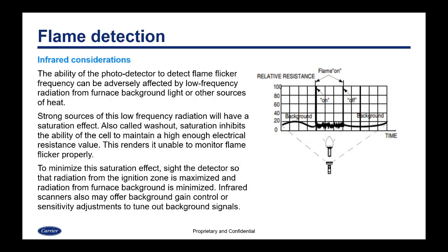The ability of the photo detector to detect flame flicker frequency can be adversely affected by low frequency radiation from furnace background light or other sources of heat. Strong sources of this low frequency radiation will have a saturation effect, also called washout — saturation inhibits the ability of the cell to maintain a high enough electrical resistance value, rendering it unable to monitor flame flicker properly. To minimize this, sight the detector so that radiation from the ignition zone is maximized and radiation from furnace background is minimized. Infrared scanners may also offer background gain control or sensitivity adjustments to tune out background signals. Narrowing the field of view to the flame you need to see can mitigate a lot of that background radiation.